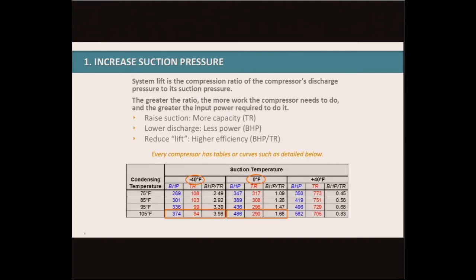Going into the first one — increasing suction pressure. To define suction pressure and lift: system lift is a compression ratio of the compressor's discharge pressure to its suction pressure. The greater the ratio from suction pressure to discharge pressure, the greater amount of energy the compressor utilizes. So if we have a larger ratio with a lower suction and a higher discharge, it uses much more energy. If we're able to increase our suction and/or decrease our discharge, then we're using less energy for our compressors.